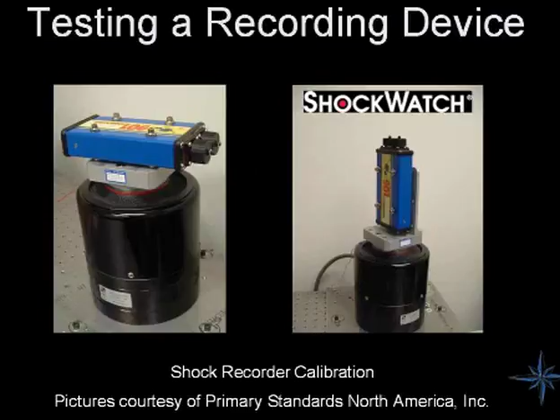And you've probably seen that picture before from previous presentations. If not, this is a real example from a customer. They are a calibration laboratory, and the blue box you see here is a shock recorder made by a company called Shockwatch, and that shock recorder is on top of a custom-made table that we made. That table has an internal accelerometer, just like our air bearing shaker, and that's all sitting on top of the 2075E shaker. And the customer can calibrate the shock recorder in the vertical and horizontal position. So again, shaker table, and here's the solution that we offer.